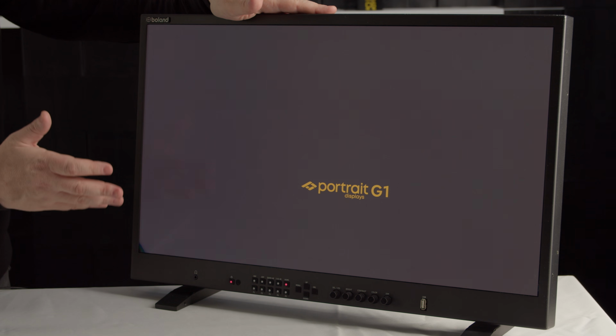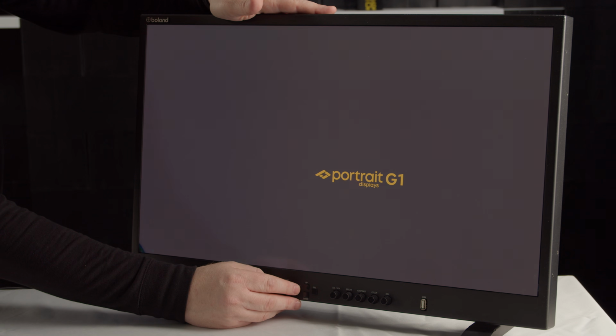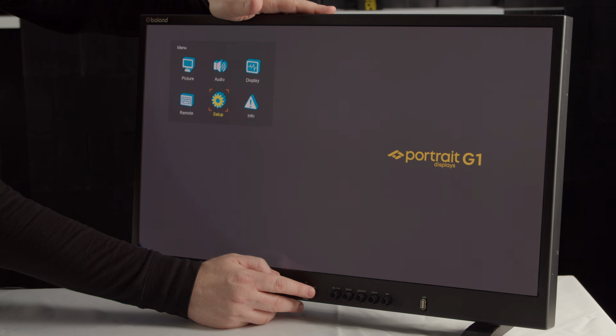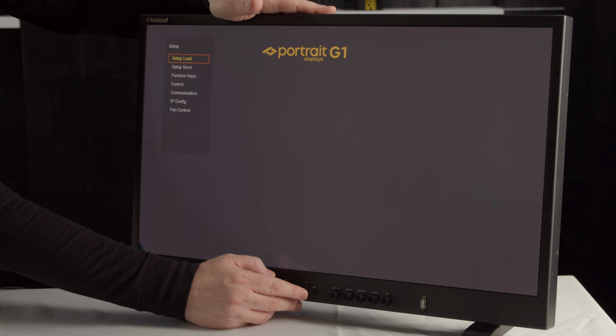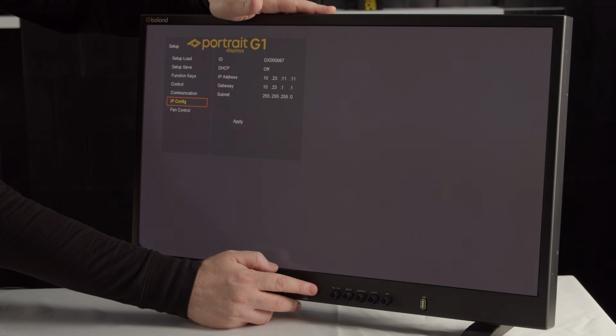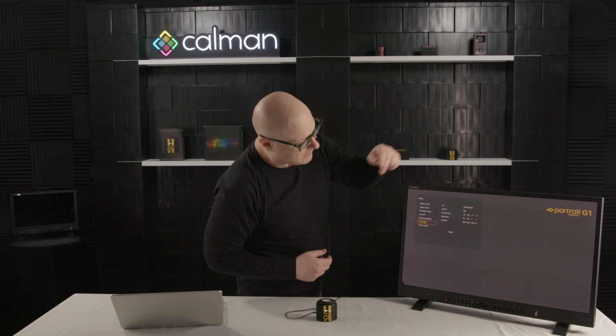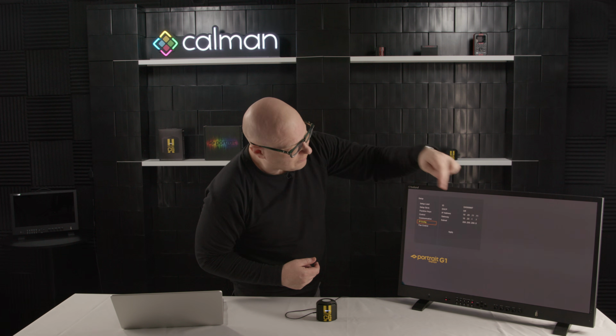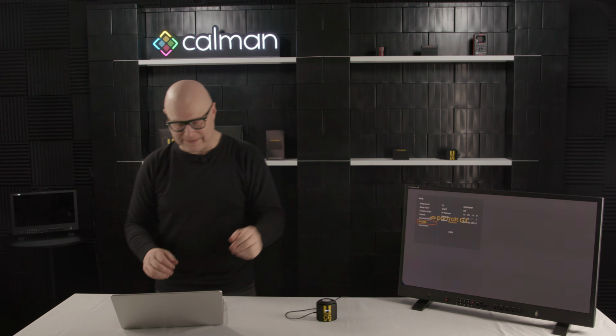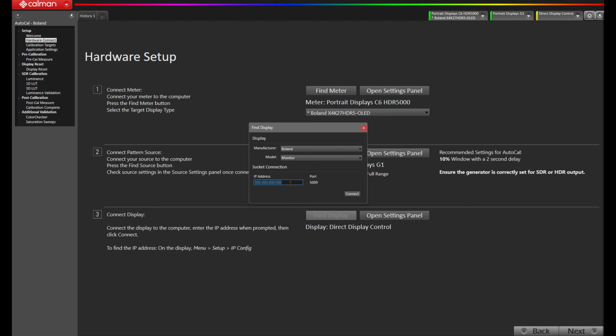With the display reset to the factory state, I can now come back and see where my IP address is. Let me press Menu and arrow over to Setup, press Select, and come down to IP Config. This is where you're going to be able to get your IP address to enter into Calman. My IP address is 10.23.11.11, so let's come back to Calman and enter that address.